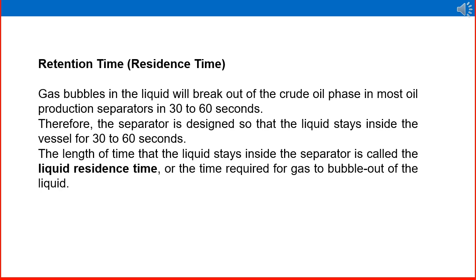Residence time: gas bubbles in the liquid will break out of the crude oil phase in most oil production separators in 30 to 60 seconds. Therefore, the separator is designed so that the liquid stays inside the vessel for 30 to 60 seconds. The length of time that the liquid stays inside the separator is called liquid residence time, or the time required for gas to bubble out of the liquid.